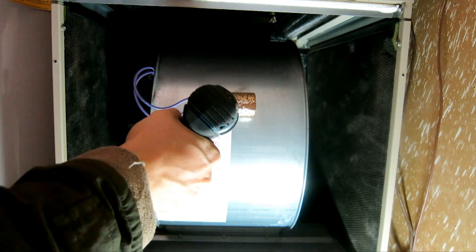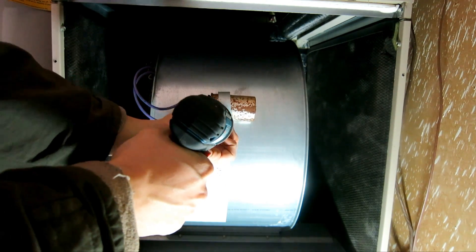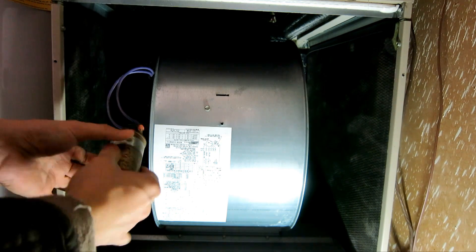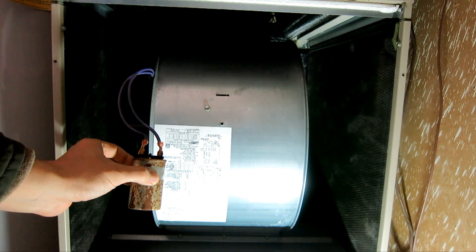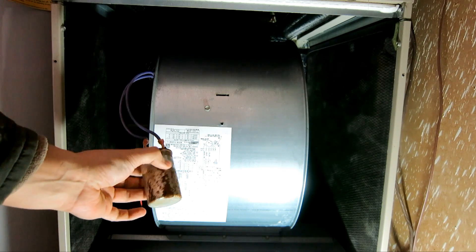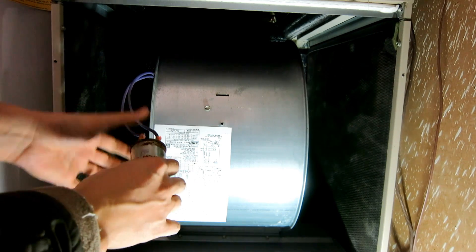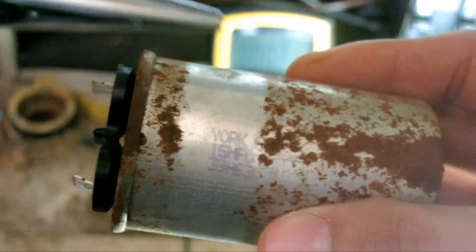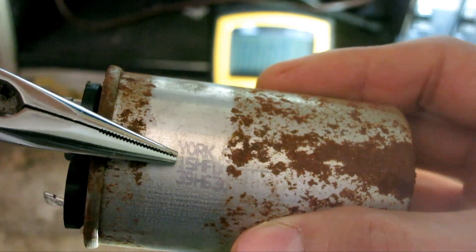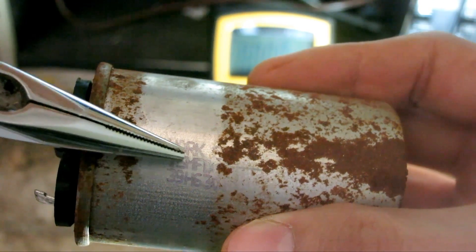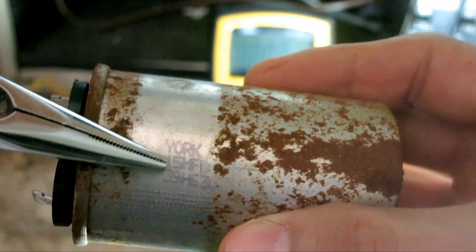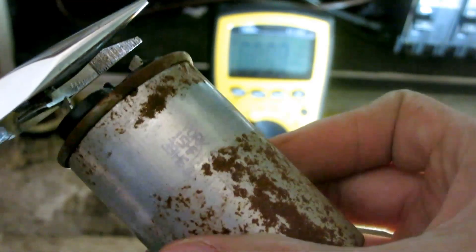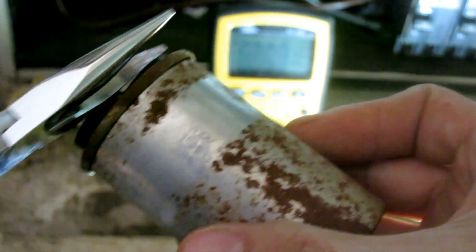Since I want to test the capacitor, I'm going to remove it so I can identify the capacitance, and I'll remove it from the leads. It doesn't matter how it connects. As you can see right here, it says this is a 15 microfarad mfd. Before I measure, I also want to discharge the capacitor with something metal.